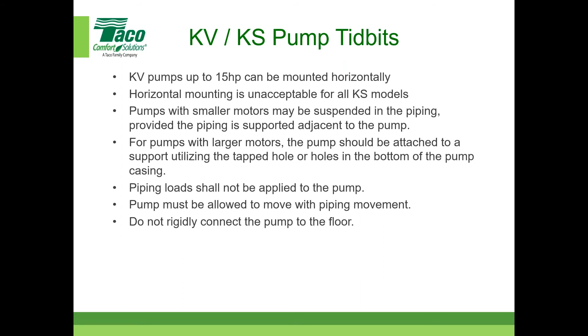These are just tidbits I wanted to mention. Do not rigidly connect the pump to the floor. If you're going to put it on a stand, let that stand slide just a little bit. This isn't just a KS/KV pump tidbit, but I recommend, and maybe it should be in your specifications, that you pipe away from pumps. Don't pipe to the pump and then use a big screwdriver to align the flanges, because something bad's going to happen. So pipe away from it.